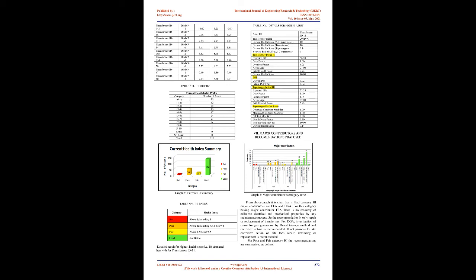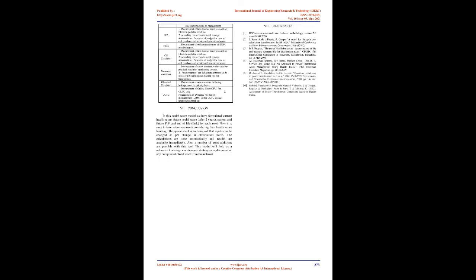Future health score: The aging rate is first recalculated for calculation of future health score. The initial health score was calculated using an initial aging rate based on the asset expected life, duty, and location. The current health score also takes into account the condition information and, as such, recalculating the aging rate using the asset age and the current health score gives a more accurate indication of the expected future aging of an asset.